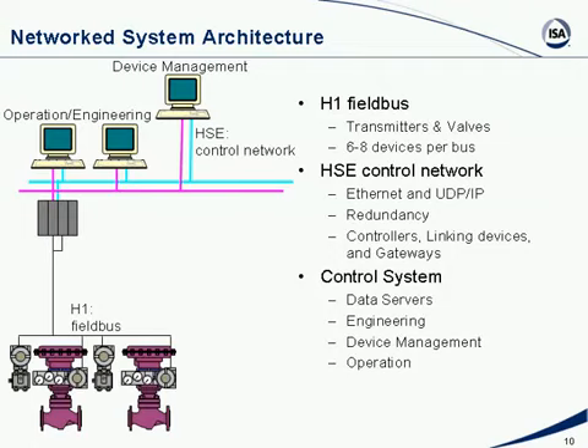Okay, so this means that non-essential communication doesn't interfere with the real-time communication. Okay, and this is actually unique for Foundation field bus. And it's very, very important to have that for PID control. Buses where the communication is so-called free running are not really suitable for PID control because they are not precisely periodic and they are not synchronized. Okay, that results in too much jitter, etc., which is not good for PID control. So for devices used in PID loops, Foundation field bus is really the protocol of choice.